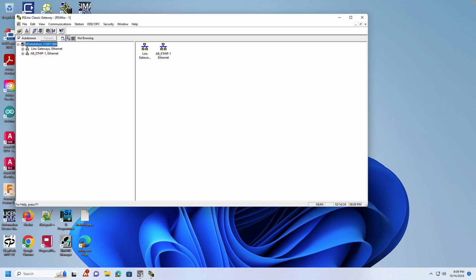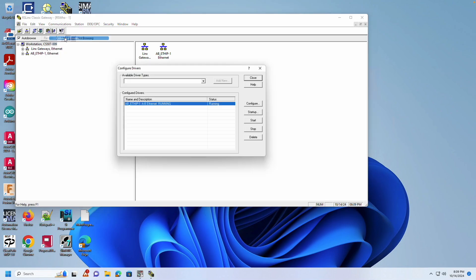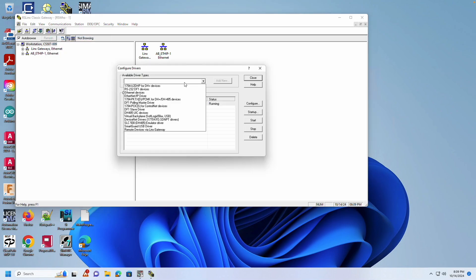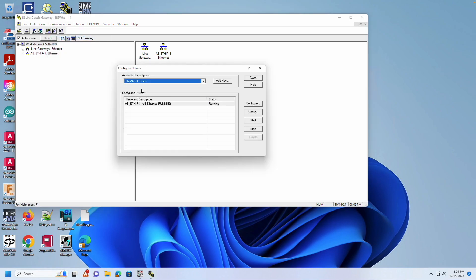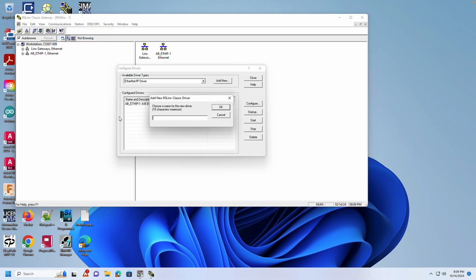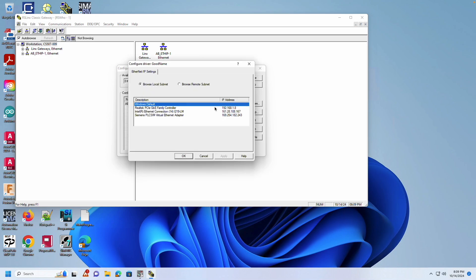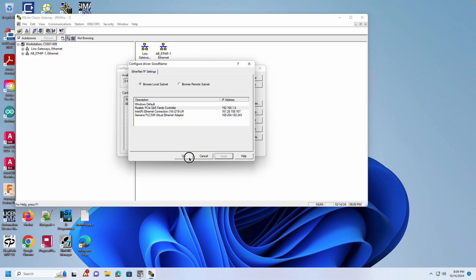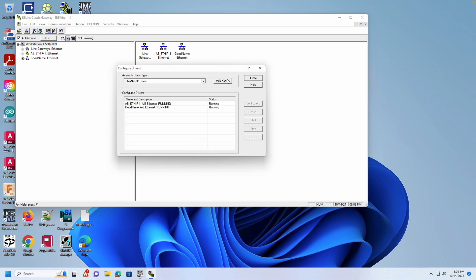Now, open RSLinx. In RSLinx, create a new driver for simplicity. When creating the new driver, choose a meaningful name so you can easily identify it later. In the Configuration dialog box, make sure you select the interface that the PLC is attached to.